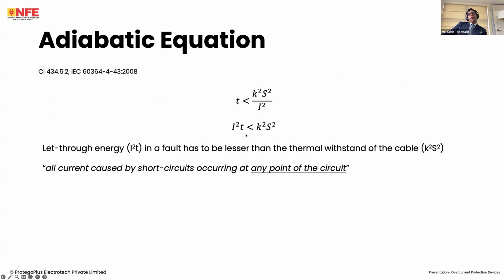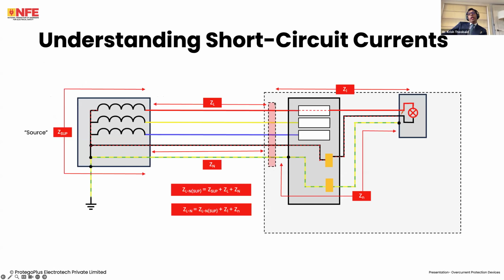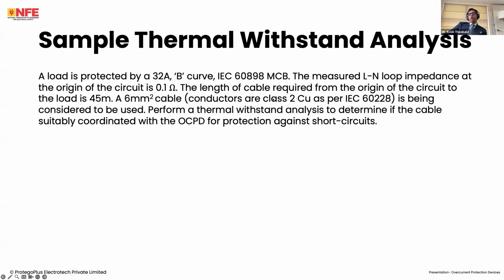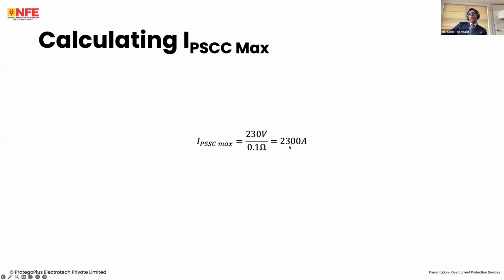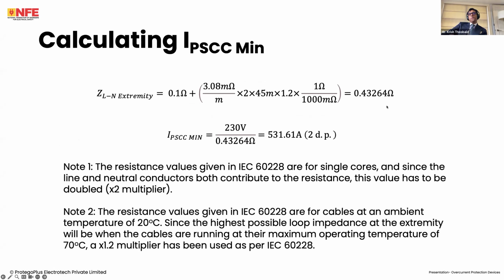Okay. We know at this point 0.1 ohms. What is the short circuit current here? Single phase short circuit current, 230 divided by 0.1 ohms, 2300 amps. That is the maximum possible short circuit current.